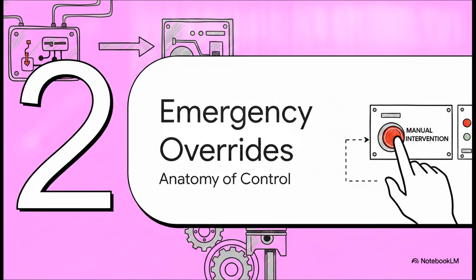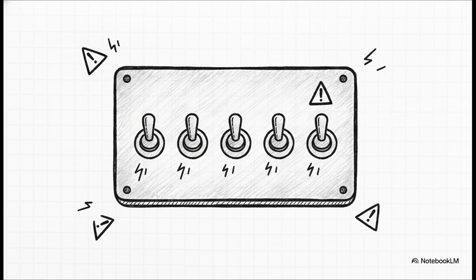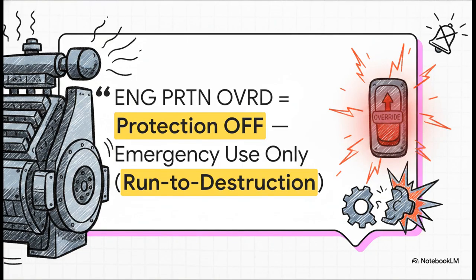Moving right along to Section 2, the emergency override panel and the anatomy of control. Because let's face it, sometimes even the smartest automated logic in the world needs a human operator to step in and take direct control. And that is exactly where this override panel comes into play. What's really fascinating here is seeing all 5 of these distinct override switches clustered together. Each one gives a technician the ultimate authority to bypass protective logic. We've got crank override for directly engaging the starters, engine protection override, manual pre-lube, low idle select for controlled warm-ups, and rapid start/stop to toggle high-speed sequencing. Make no mistake, every single one of these switches dramatically changes the engine's default behavior. Now, we really need to slow down for a second and emphasize the engine protection override.